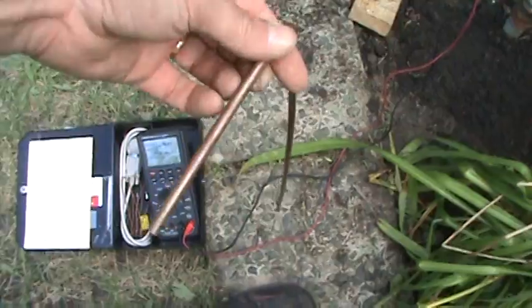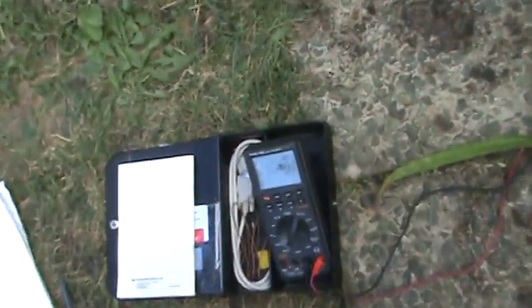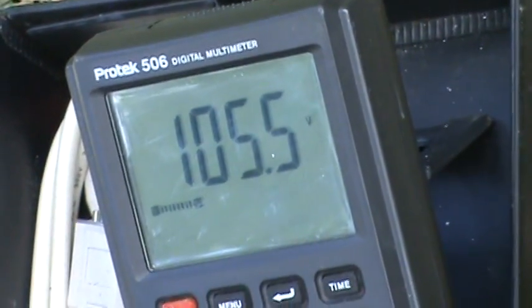We're back up to 103 volts. Now I want to show you again with this copper rod here — I'm going to start putting that down the side and show you the results. 104, then 3. Putting it down a couple inches: 5, 4, 5. It's going up.